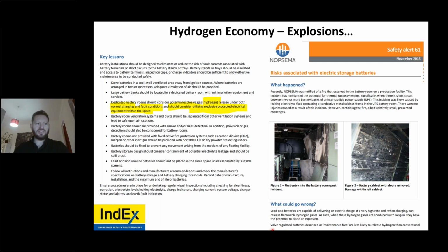But the problem in the industry is that these valve regulated batteries are described as maintenance free, and they're less likely to produce hydrogen. Now the problem is that when people see maintenance free, well, human factors again, oh, we don't have to do anything. That is incorrect. That is unsafe. So the manufacturers using the word maintenance free, in my view, cause these human factor issues. If they would say reduced maintenance, but be aware of produced hydrogen, that would be much safer.